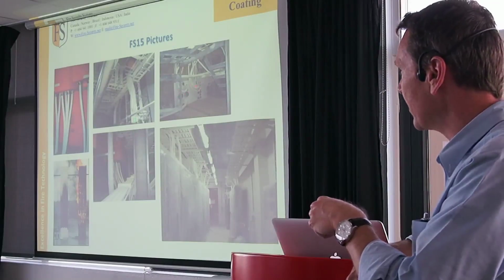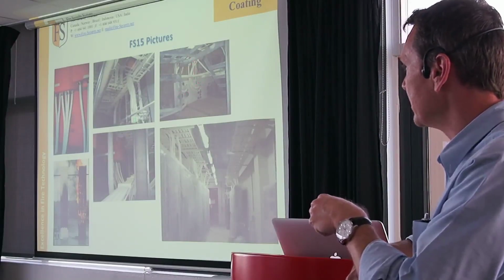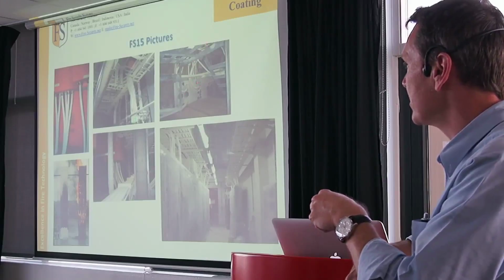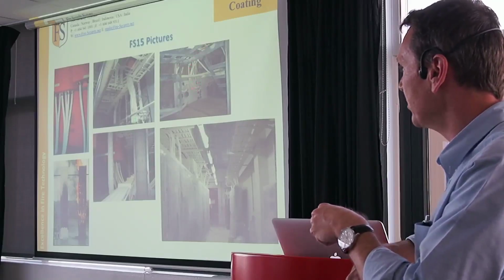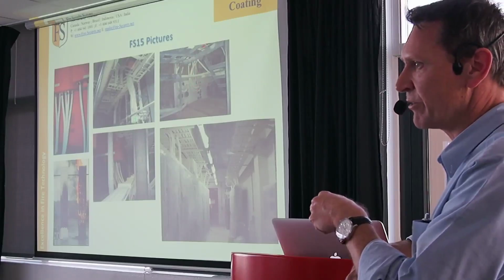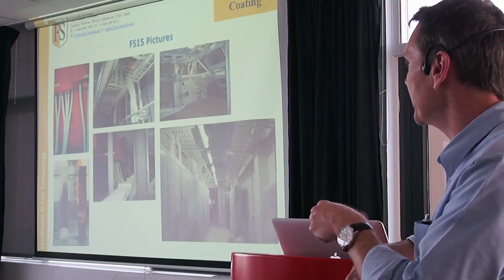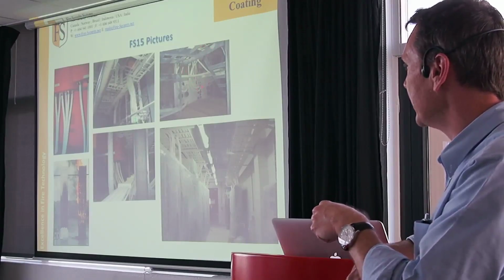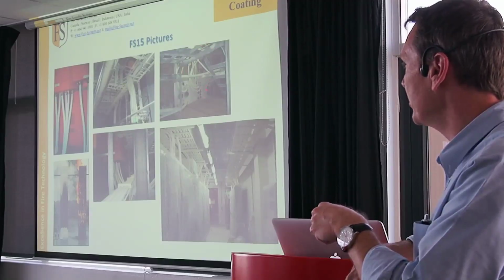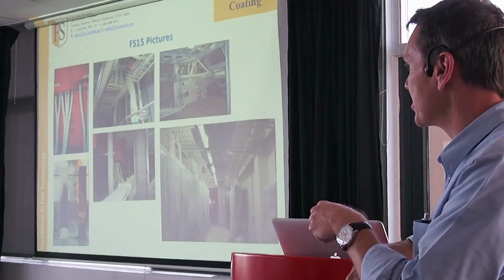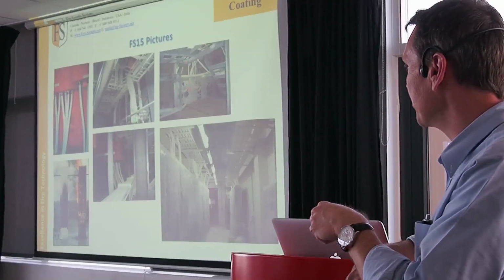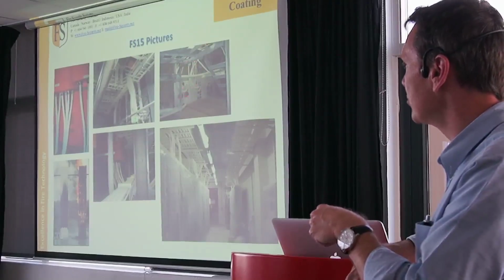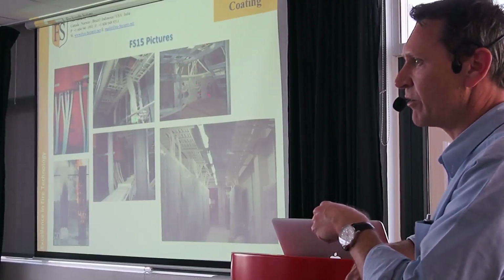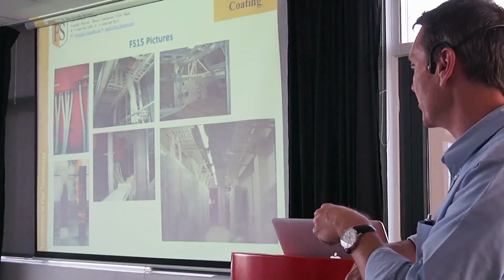But what they've done is they've coated the cables in this scenario, so there's zero flame spread down through the cable and up into the yard or up into another area, and vice versa as well. So the cable conduits are open for water because it's below ground, and the cables are coated for no spread of flame, and these don't need to be sealed or fire rated because we've used cable coating to stop that flame spread.